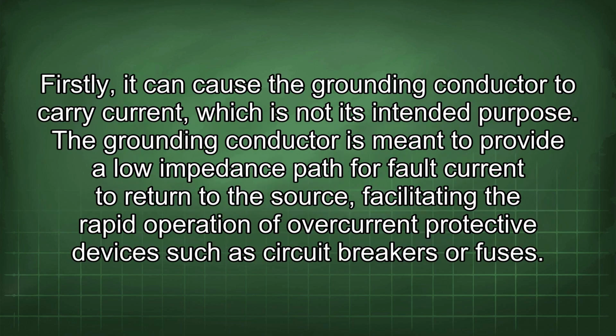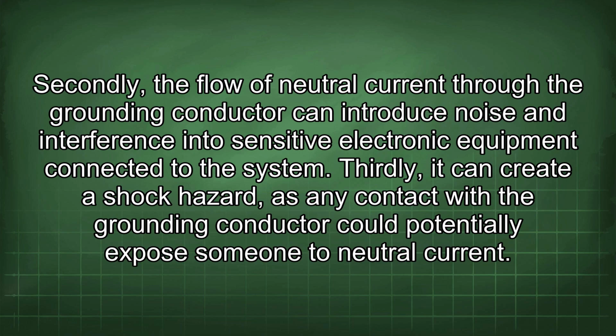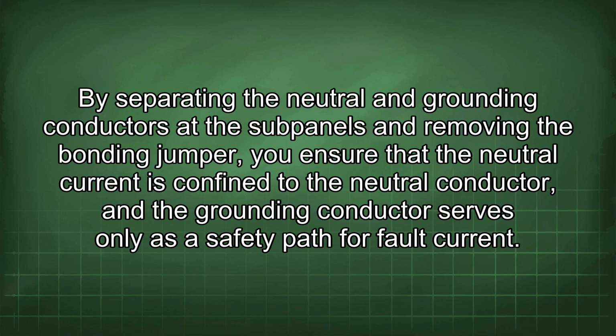Firstly, it can cause the grounding conductor to carry current, which is not its intended purpose. The grounding conductor is meant to provide a low impedance path for fault current to return to the source, facilitating the rapid operation of overcurrent protective devices such as circuit breakers or fuses. Secondly, the flow of neutral current through the grounding conductor can introduce noise and interference into sensitive electronic equipment connected to the system. Thirdly, it can create a shock hazard, as any contact with the grounding conductor could potentially expose someone to neutral current. Separating the neutral and grounding conductors at the subpanels and removing the bonding jumper ensures that the neutral current is confined to the neutral conductor, and the grounding conductor serves only as a safety path for fault current.